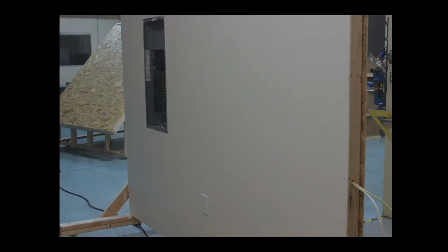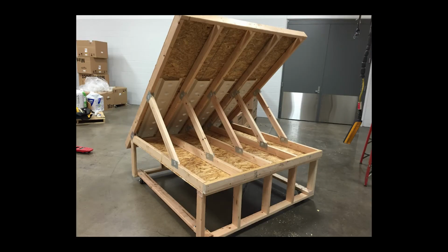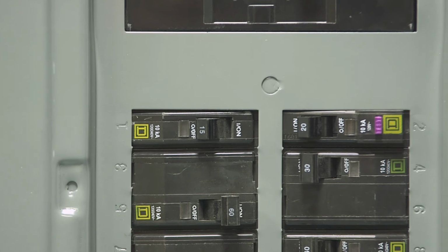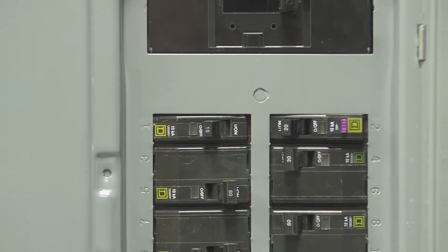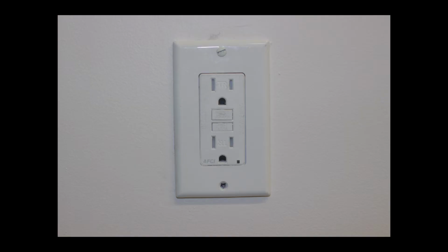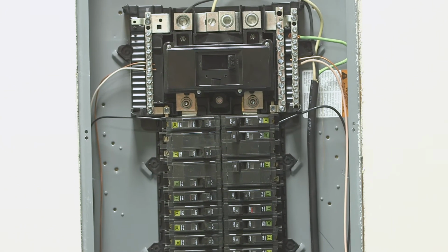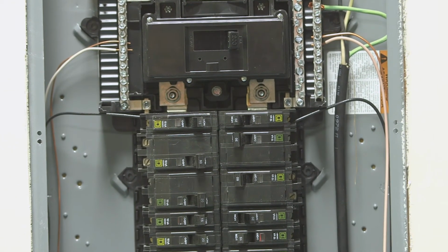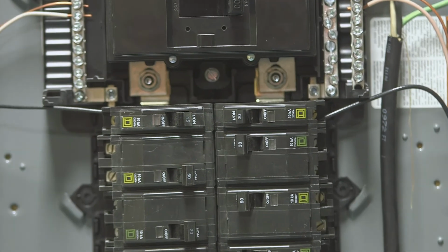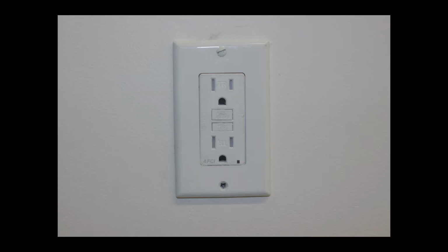We built two models with non-metallic, or NM, cable. The tests were conducted at a UL-approved test lab. In the first test, an AFCI circuit breaker was installed in the panel, and an AFCI receptacle in the first outlet box. In the second test, a standard circuit breaker was installed in the panel. In these tests, we discovered what would happen if a homeowner were to accidentally drive a screw into a cable when installing shelf brackets on the wall, causing an arcing condition.